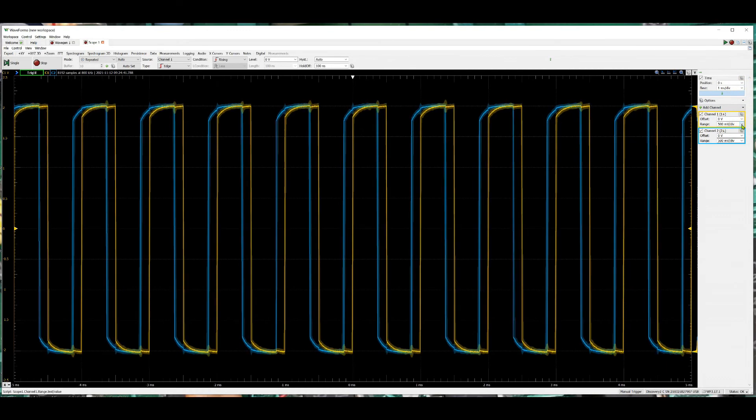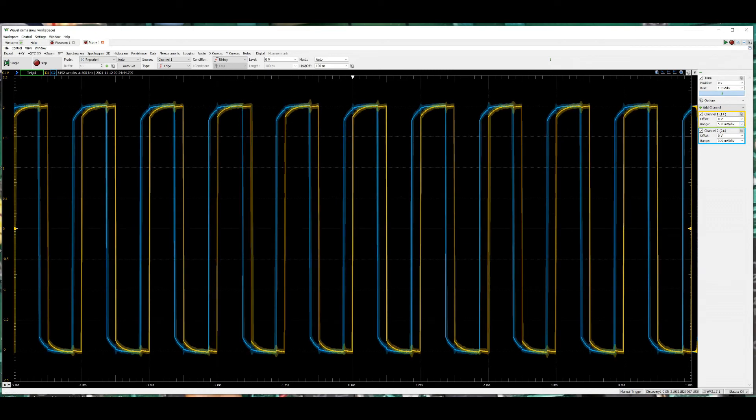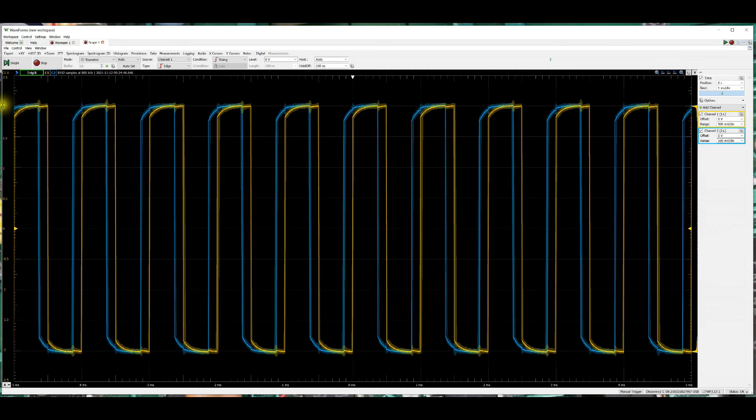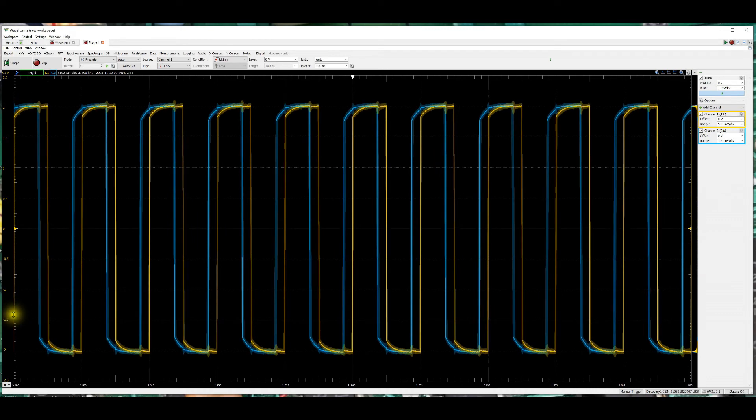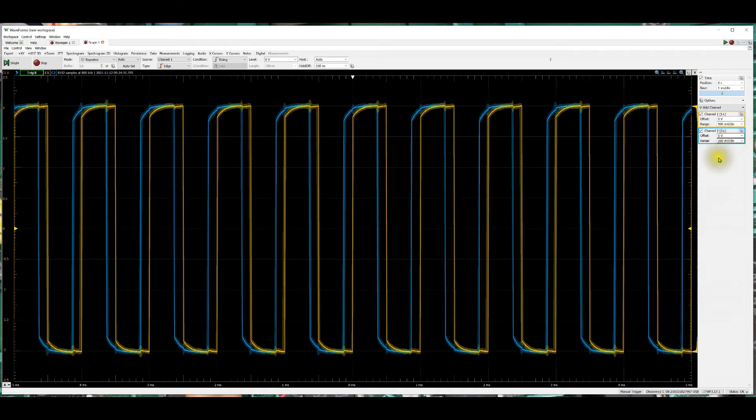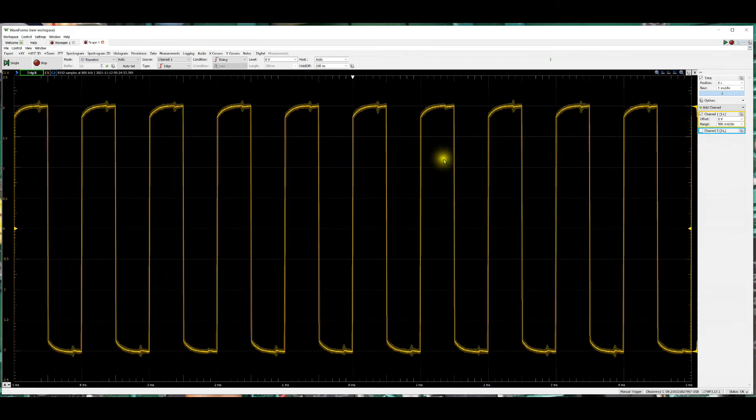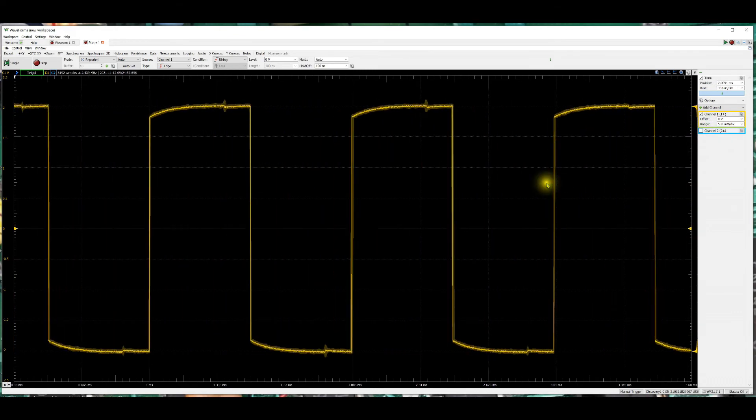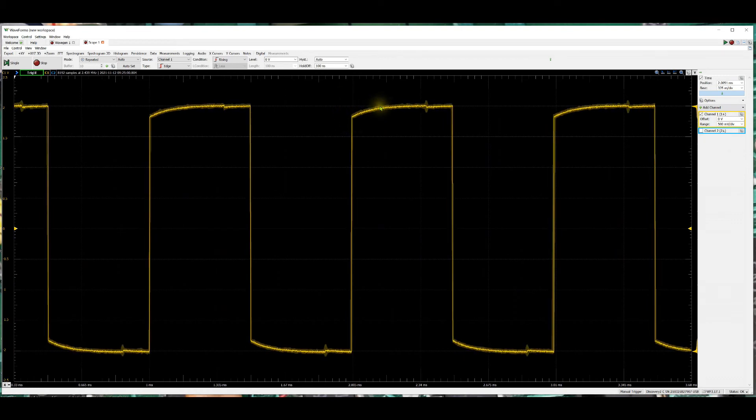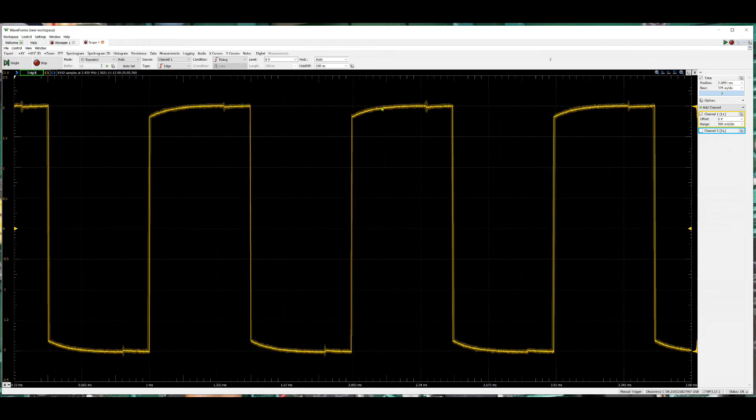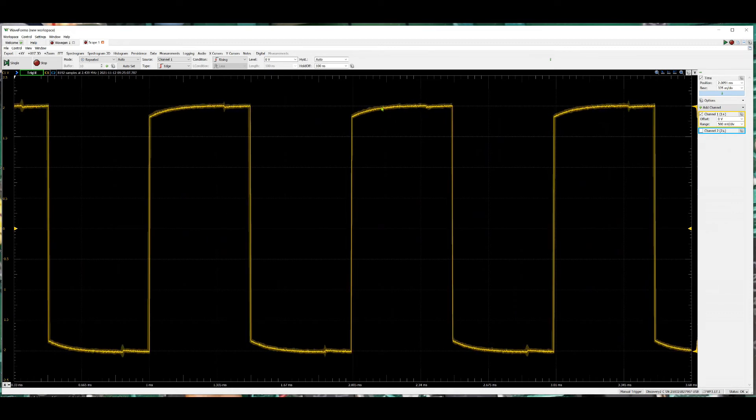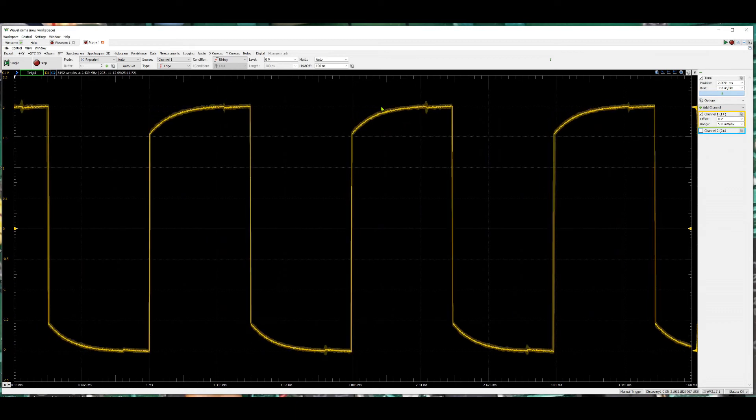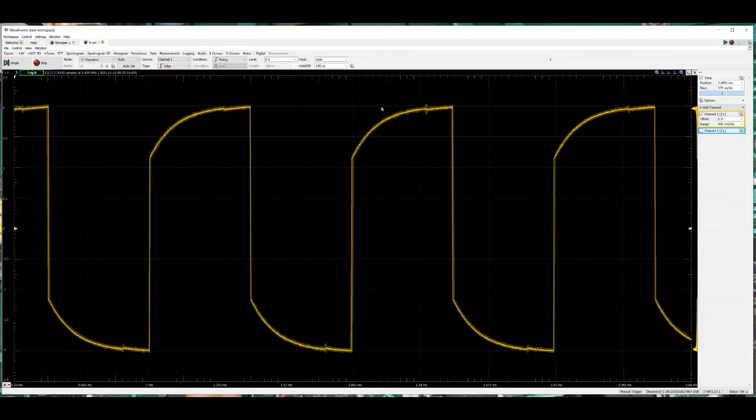I'm going to make a couple other changes here. They're set to 500 millivolts per division. So there's plus two volts, there's minus two volts. I'm going to go ahead and turn channel two off. We can see the yellow is channel one. Let's go ahead and zoom in here a bit and get a look at this. So this really should come up and be square. Now I'm going to take the adjustment tool and I'm going to get into that little trimmer capacitor on the probe, and I'm going to rotate it through its full rotation.